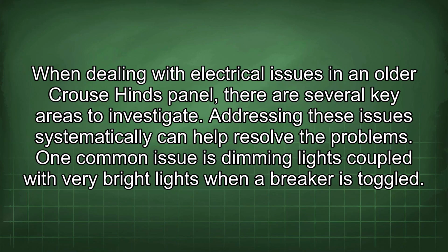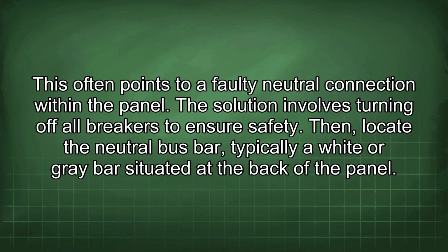When dealing with electrical issues in an older Crouse Hinds panel, there are several key areas to investigate. Addressing these issues systematically can help resolve the problems. One common issue is dimming lights coupled with very bright lights when a breaker is toggled. This often points to a faulty neutral connection within the panel.